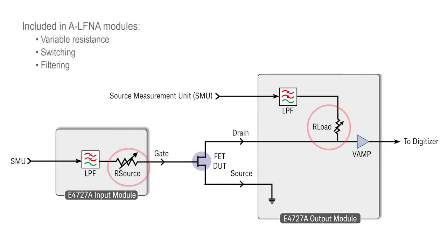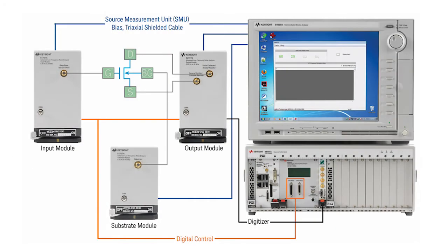The variable resistance, switching, and filtering functions are included in the remote ALFNA modules, which will be placed close to the device under test, so as to minimize the cable capacitance and electromagnetic noise.